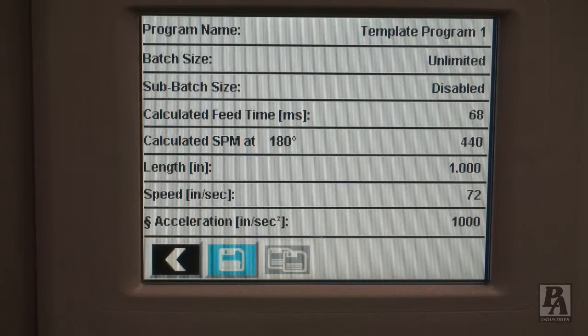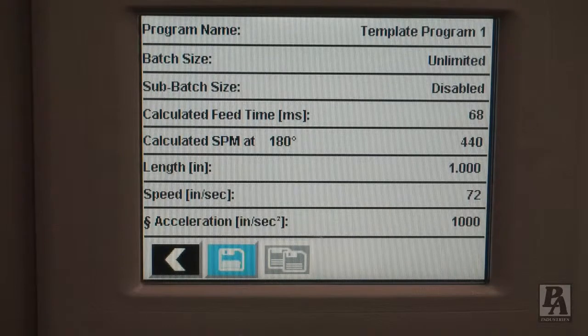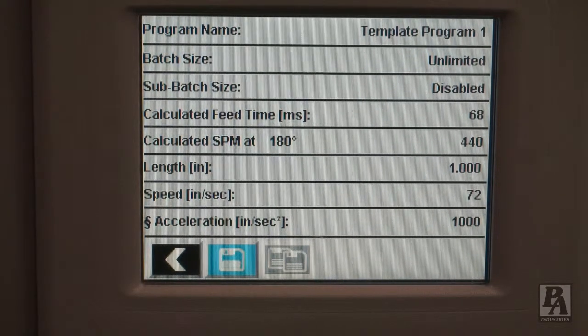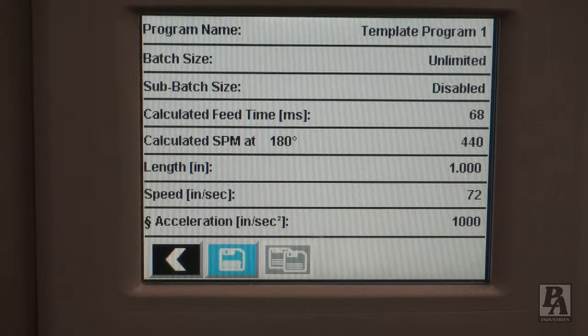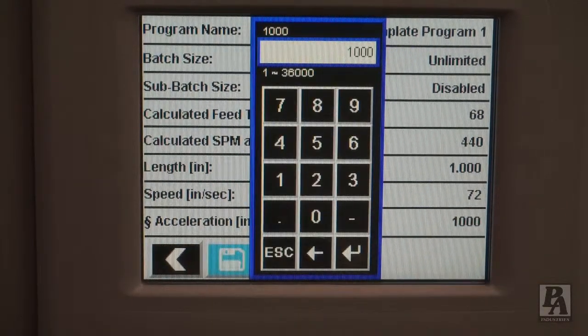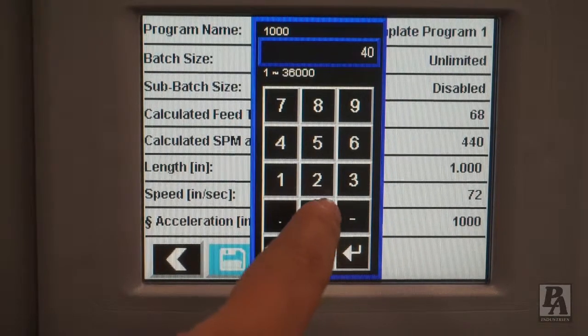There are a few possible causes of an excess velocity error. In rare cases, an excessively high acceleration can cause issues. First, be sure that the acceleration and deceleration are set to the same value. If they are already at the same value, try reducing the acceleration and deceleration.